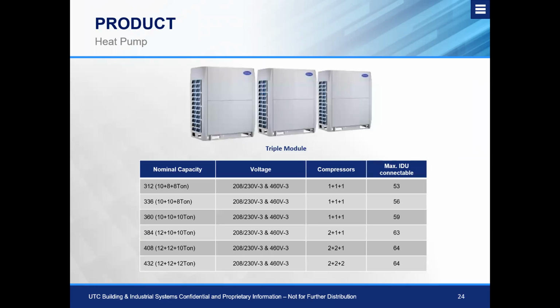And then finally on our triple module, which is going to be from our 312,000 BTU all the way up to our 432,000 BTU or our 36-ton outdoor unit, our number of compressors start to increase right around our 32-ton, which ends up with 4 compressors. On our 34-ton unit itself, we'll end up with 5 compressors. And then, of course, on our 36-ton outdoor unit, we're going to end up with 6 compressors. So obviously more coil surface area, more compressors, more low ambient heating performance. And then, of course, as we reach our last 2 tonnages, which are our 34- and 36-ton units, our maximum connectable indoor units will be 64. Okay, but again, that all varies on your outdoor unit tonnage.